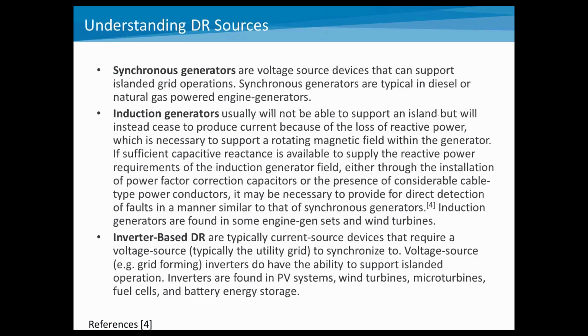Just to cover some highlights with understanding your DER, or distributed resources, there's basically three different kinds. You may have a synchronous generator, and typically these are voltage source devices, something like a diesel generator or a natural gas powered engine genset, realizing that those can definitely support island grid operations. Induction generators typically are not able to support an island, and this is because of the need for reactive power to supply on an induction generator. Of course, if there is sufficient capacitance, like capacitor banks inside that potential island, that needs to be evaluated.